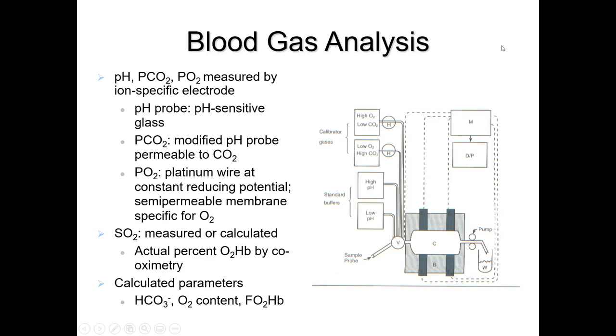For blood gas analysis, pH, pCO2, and pO2 can be measured by ion-specific electrodes. The pH probe uses pH-sensitive glass; the pCO2 electrode is a modified pH probe permeable to CO2; and the pO2 electrode uses a platinum wire at constant reducing potential with a semi-permeable membrane specific for oxygen. Oxygen saturation is measured or calculated as the actual percent of oxyhemoglobin by co-oximetry. Calculated parameters include bicarbonate, oxygen content, and fO2Hb.